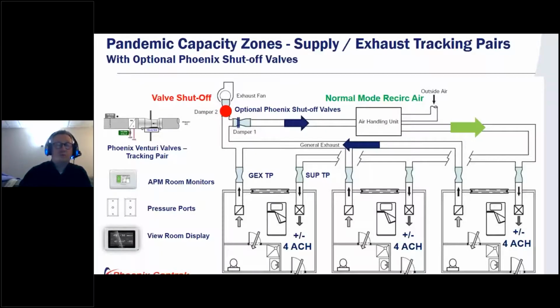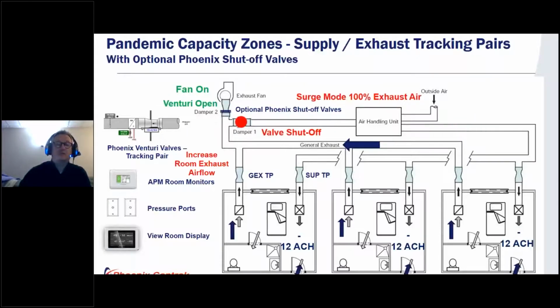And then we directly pull the negative air out of those patient rooms, just like this. So again, the valve shuts off to recirculating, the fan opens up, we increase our exhaust air by around 15%. We ramp it up from 4 air changes to 12 air changes, providing negative pressure, all within either a scheduled type of situation or it can be initiated at the view monitor. Again, monitoring that room is really important. Also being able to supply some makeup air to compensate for that additional exhaust air that we're pulling out of the patient room. Okay, so that's what it would look like.